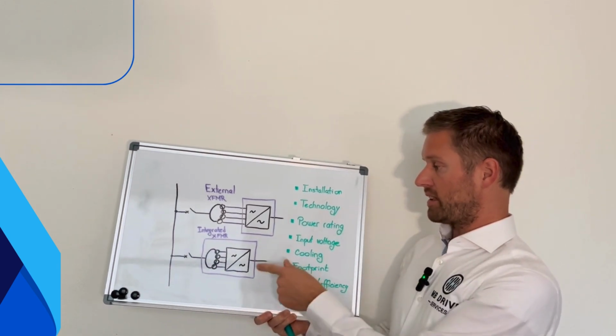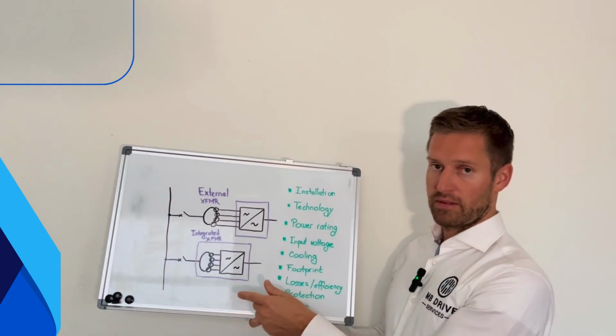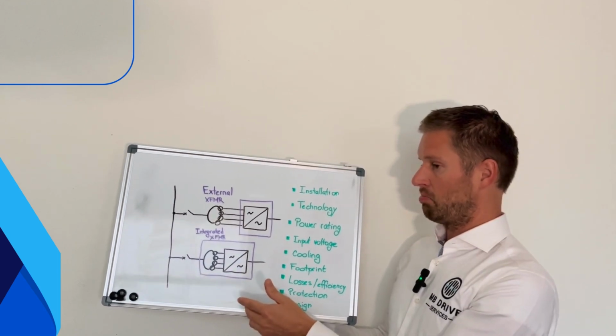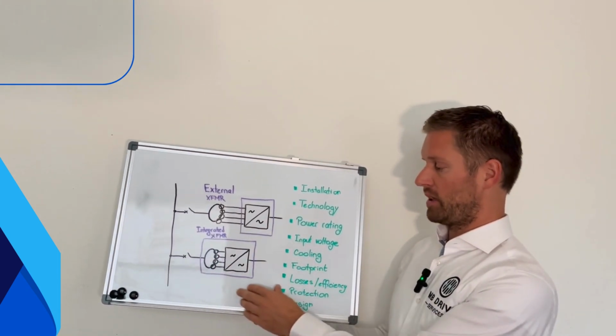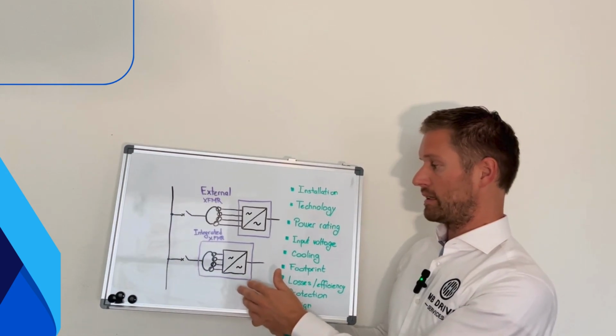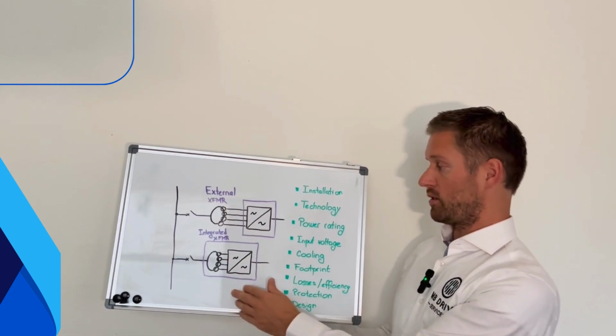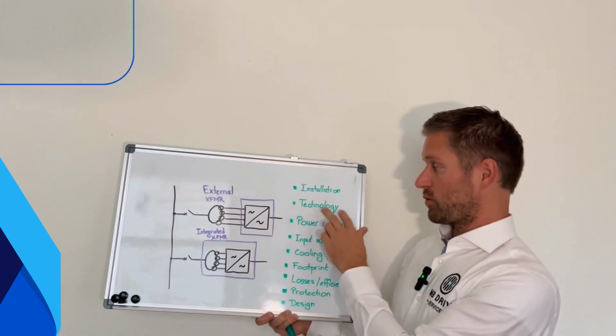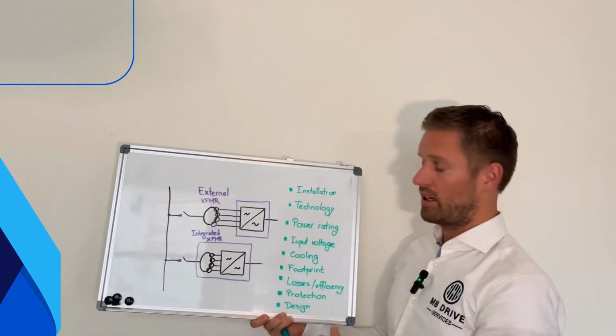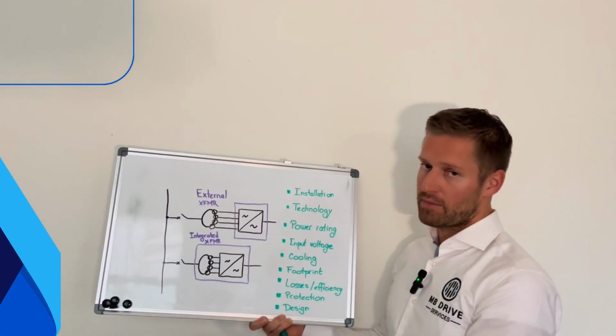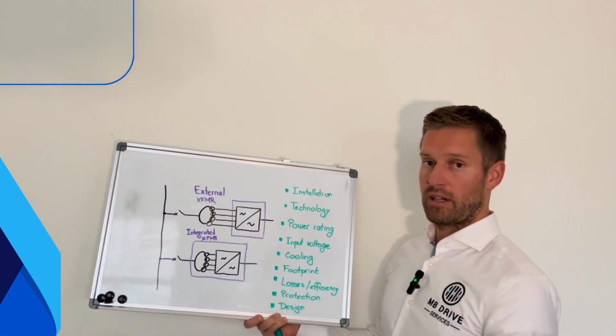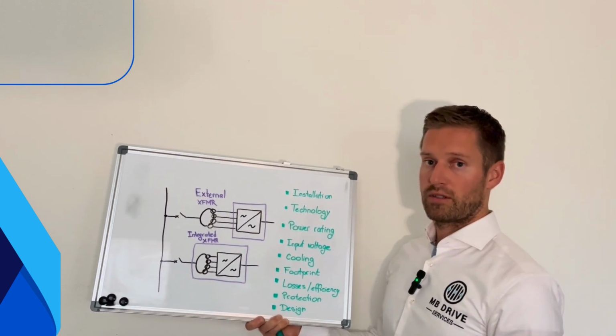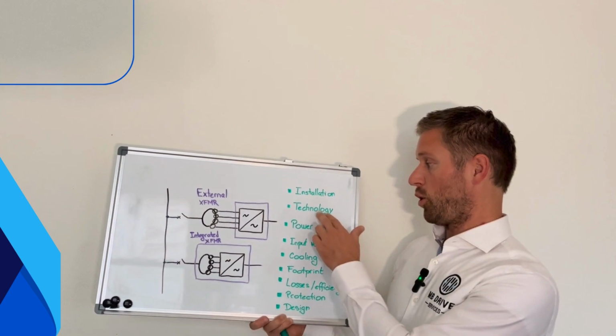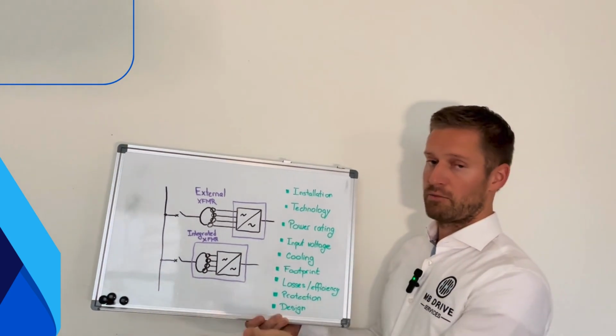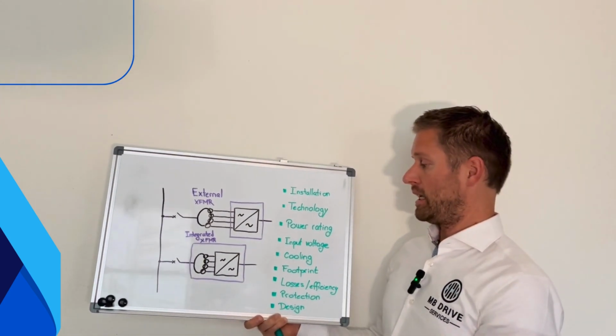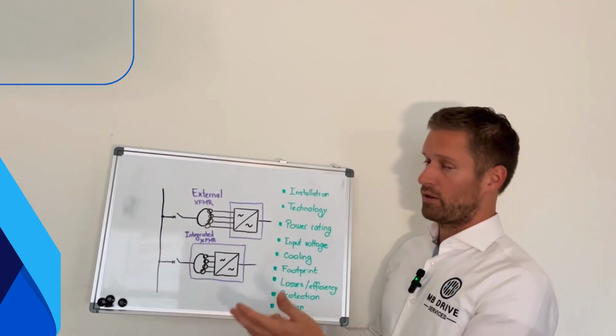Regarding technology, the integrated transformer is dry type, so it's VPI, maybe also cast resin, but typically VPI technology, so vacuum pressure impregnated dry type transformer in that enclosure. For the external transformer, we can have any technology or type of transformer. We can have dry type theoretically as well, dry type indoor, dry type outdoors with corresponding enclosure suitable for outdoor installation, or liquid immersed transformer, either with mineral oil or with some synthetic liquid or biodegradable liquid.